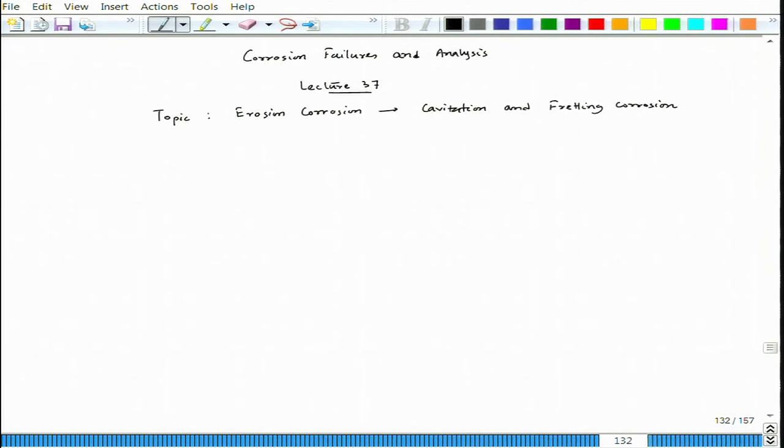Cavitation damage happens when a bubble collapses on top of a metal surface, leading to micro-jet impact on the metal surface and also shock waves. That leads to deformation on the material, and that deformation can damage the passive film before it gets repassivated, or the deformed surface can undergo extra corrosion damage before another bubble forms. This bubble is not an air bubble — it happens due to boiling of fluid.